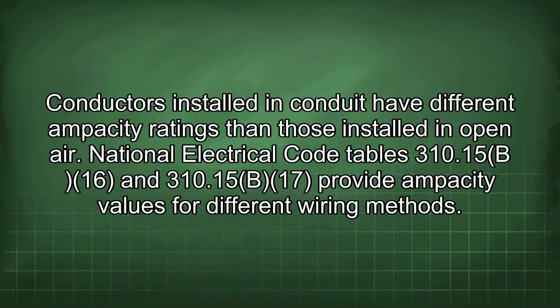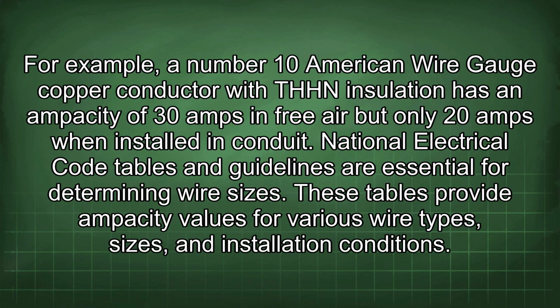National Electrical Code Tables 310.15(B)(16) and 310.15(B)(17) provide ampacity values for different wiring methods. For example, a number 10 American wire gauge copper conductor with THHN insulation has an ampacity of 30 amps in free air, but only 20 amps when installed in conduit.